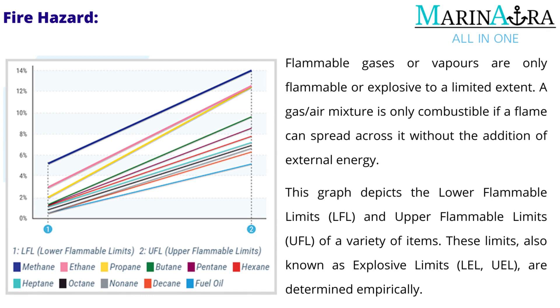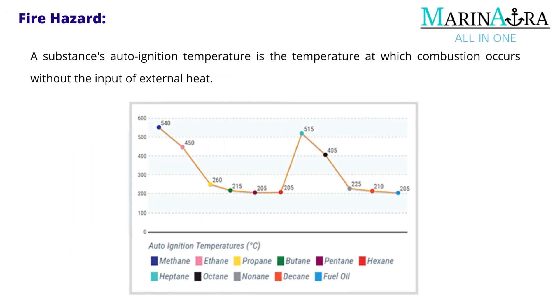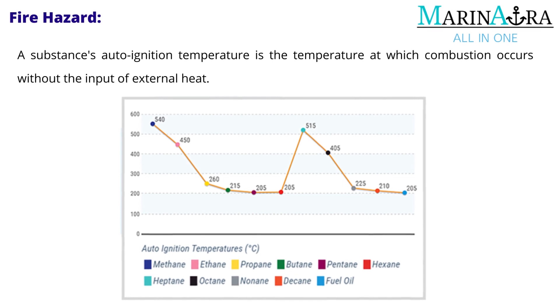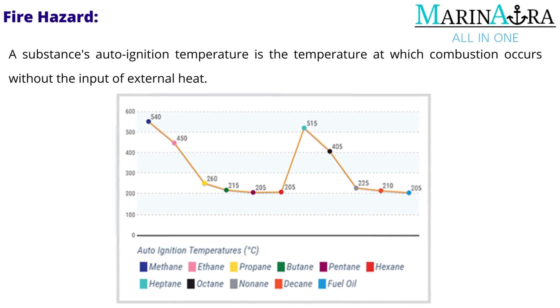Flammable gases or vapors are only flammable or explosive to a limited extent. A gas/air mixture is only combustible if a flame can spread across it without the addition of external energy. This graph depicts the lower flammable limits (LFL) and upper flammable limits (UFL) of a variety of items. These limits, also known as explosive limits (LEL, UEL), are determined empirically.